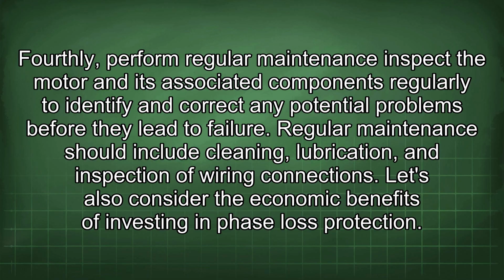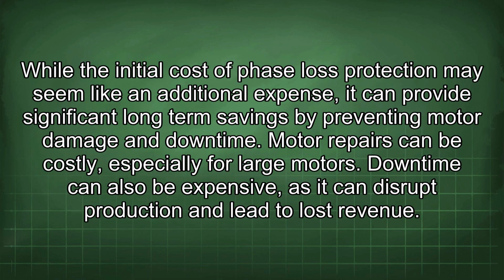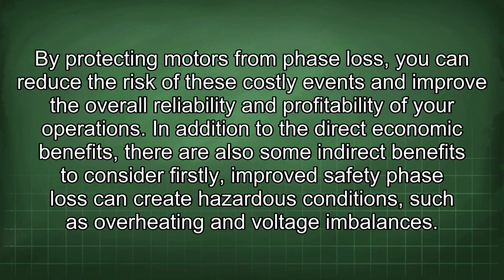Let's also consider the economic benefits of investing in phase loss protection. While the initial cost of phase loss protection may seem like an additional expense, it can provide significant long-term savings by preventing motor damage and downtime. Motor repairs can be costly, especially for large motors. Downtime can also be expensive, as it can disrupt production and lead to lost revenue. By protecting motors from phase loss, you can reduce the risk of these costly events and improve the overall reliability and profitability of your operations.